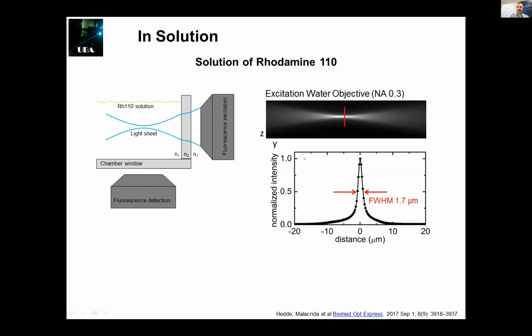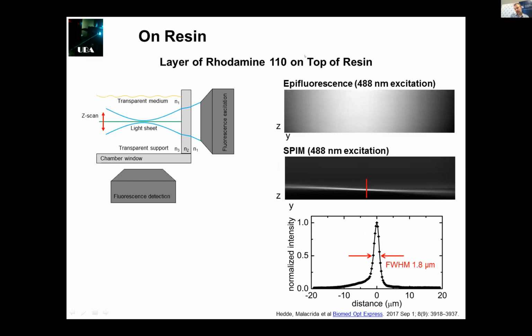So this is the performance of the light sheet in a solution. We can reach a resolution of 1.7 micrometer using 0.3 numerical aperture in the excitation beam. And in the emission, depending on the problem that we want to address, we can go from low numerical aperture to high numerical aperture with long working distance without any problem. Then we did the same calibration on the resin, and you can see that when we measure the PSF, we can reach more or less a similar full width at half maximum to what we had in the previous calibration.